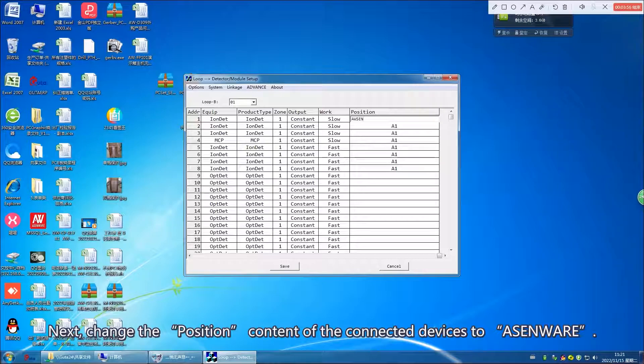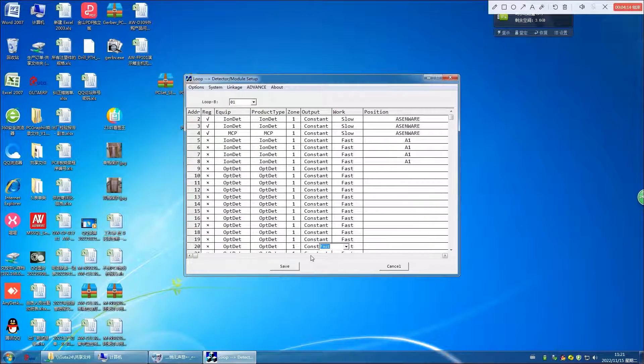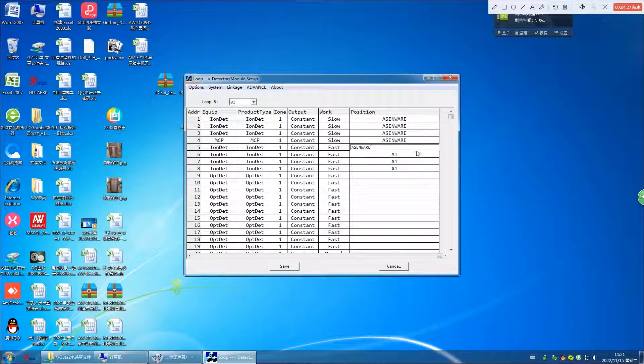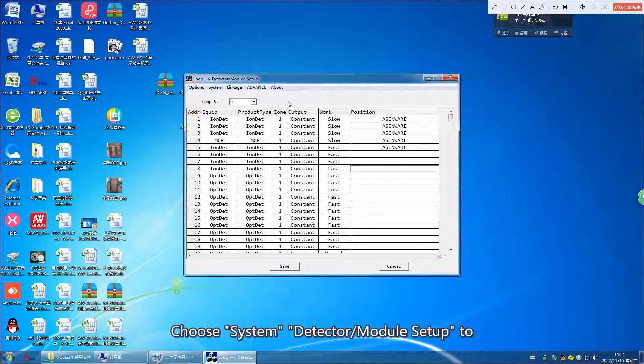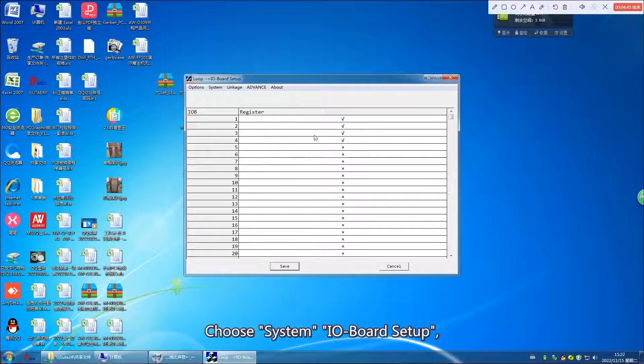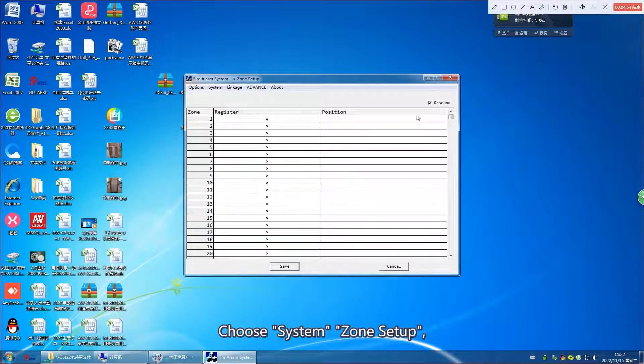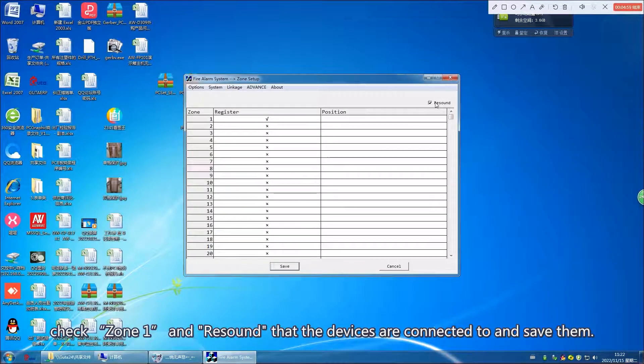Next, change the position content of the connected devices to ASENWARE. Choose System Detector / Module Setup to check whether the data is imported correctly. Then save the data. Choose System I/O Board Setup and check only the I/O Board 1 connected to the devices and save it. Choose System Zone Setup, check Zone 1 and Resound that the devices are connected to, and save them.